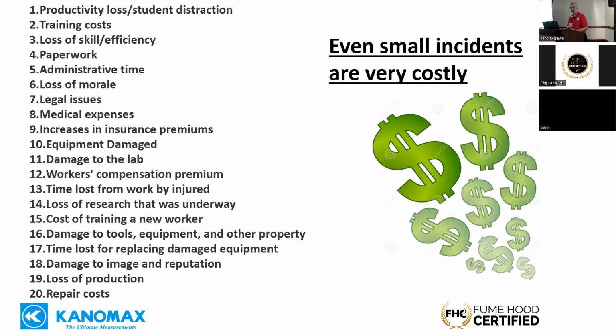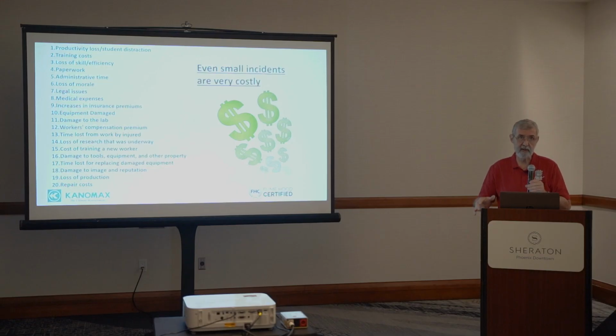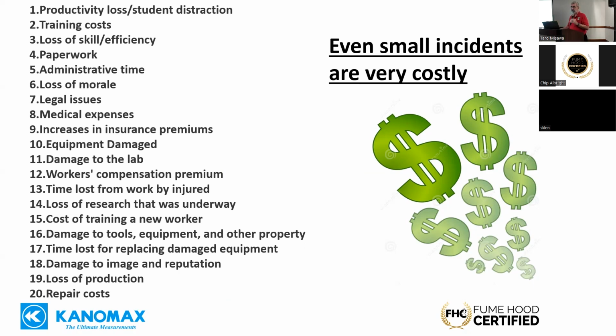And you have medical costs and all of that. Like at that university, it was a small fire isolated to one lab, and the good news was the fire brigade in the UK got there within 7 minutes of the alarm, so they started trying to extinguish it quickly. The first thing they did after that was cut the power off, and they were within 12 minutes of losing all their biological samples because the sub-zero freezers were warming up. Fortunately they got the power back on and didn't lose much of that.